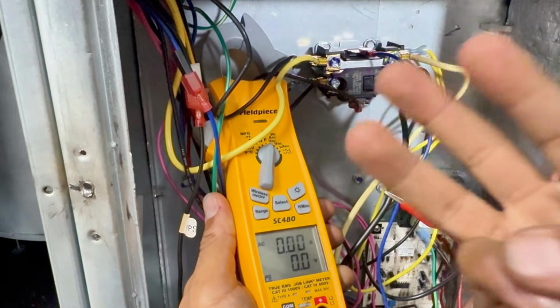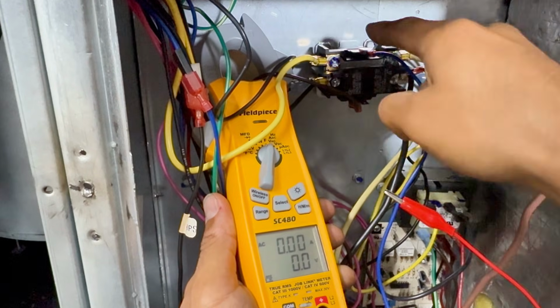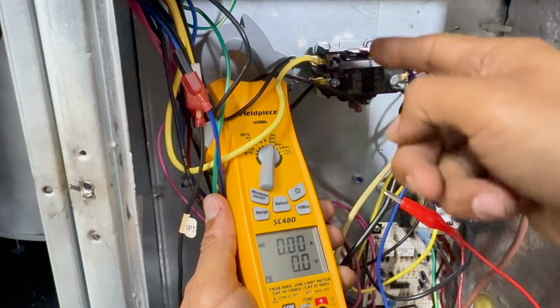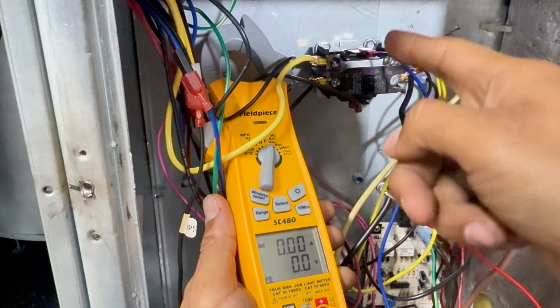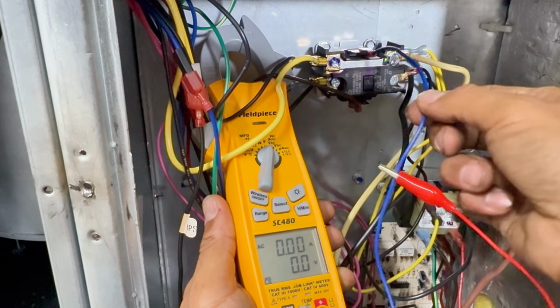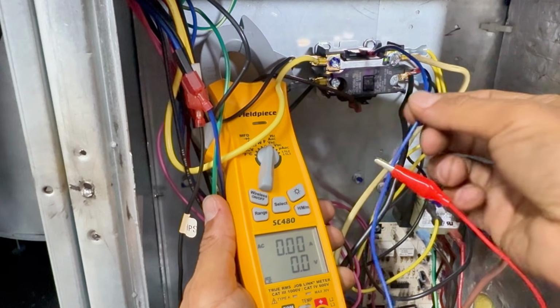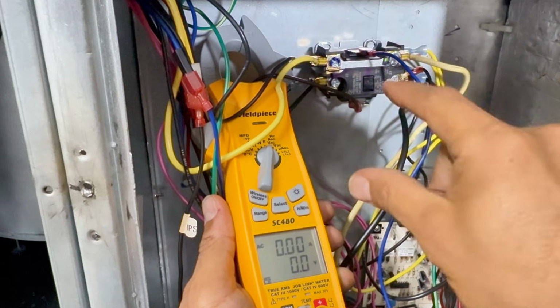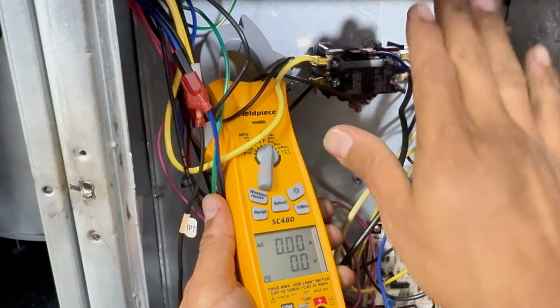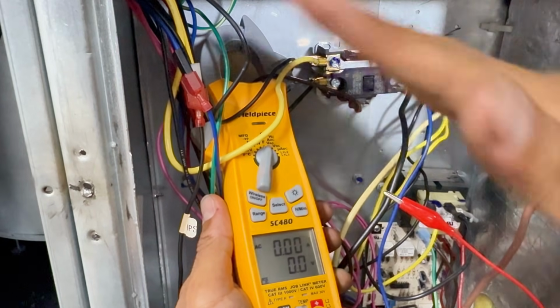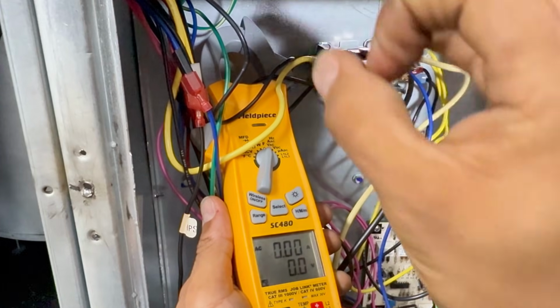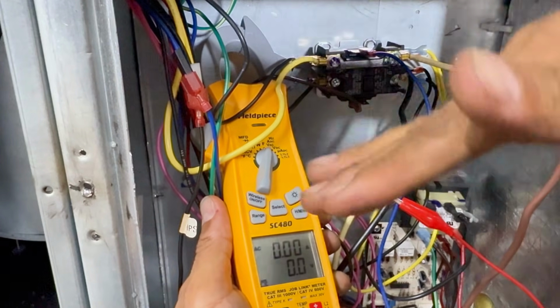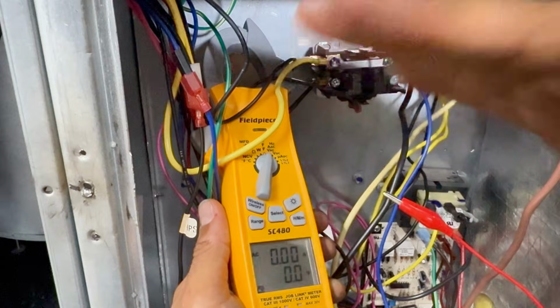Remember, I need 3 things for a circuit. I need a potential difference, which is my 24 volts. I need a load, which is my contactor coil. And I need a path for the current to travel, which is my wire. But it's traveling back and forth because of that potential of the 24 volts, right? It's going like this, 60 times a second, boom. And just imagine little balls, like on a seesaw, just flowing back and forth.